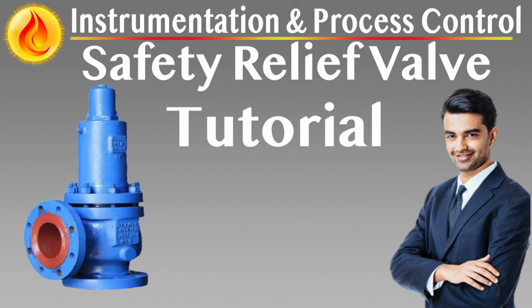Air-assisted relief valves are used to reduce the operating margin between set pressure and MOP. They incorporate a pneumatic actuator for enhanced sealing near set pressure. Three configurations exist. 1. Opening assist mode: spring set at 105% of design pressure. Valve opens reliably without instrumentation input.